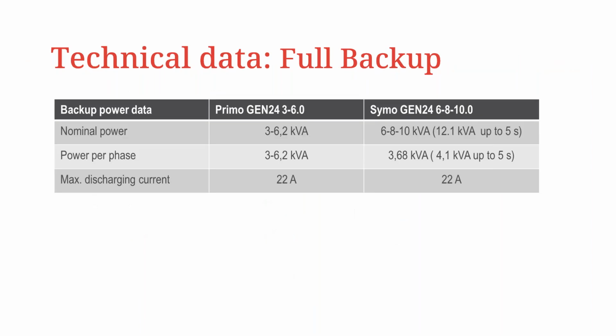So just a bit of technical data on the full backup power. On the Fronius Primo Gen 24, from power class 3 to 6, you've got a nominal power of 3 to 6.2 kVA, and then the power per phase is obviously 3 to 6.2, and your maximum discharging current is 22 amps. Whereas for the Fronius Symo Gen 24 Plus, power class 6, 8, all the way up to 10, you've got 6 to 8 and 10 kVA, which is 12 kVA up to 5 seconds. This also gives you a power per phase of 3.68 or 4.1 kVA for up to 5 seconds to allow for a higher draw current to come through. Also, your maximum discharging current is again 22 amps.